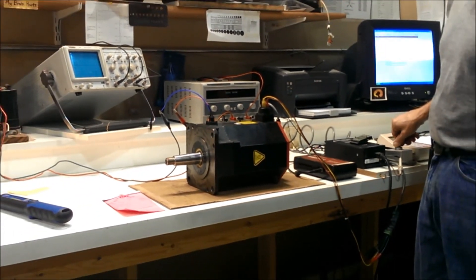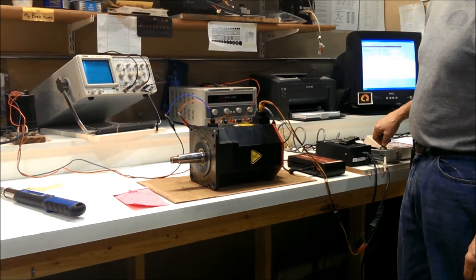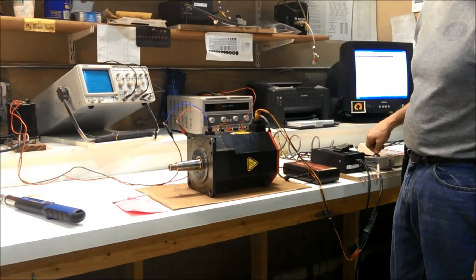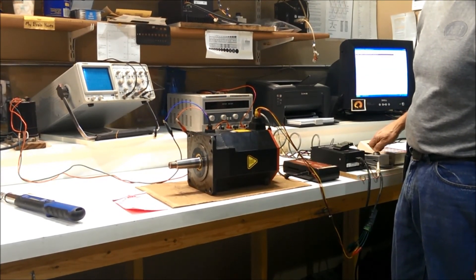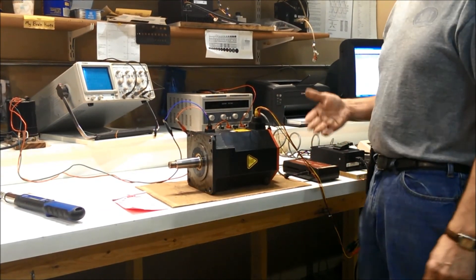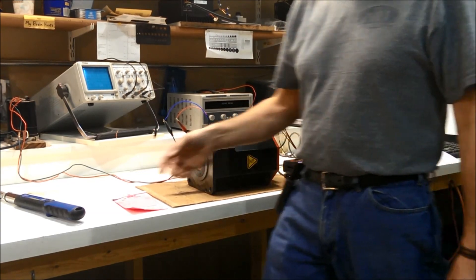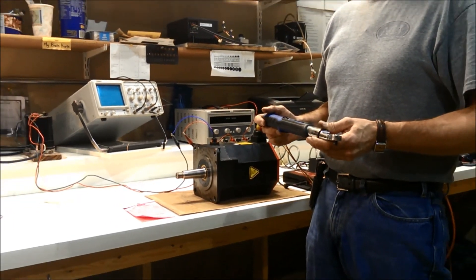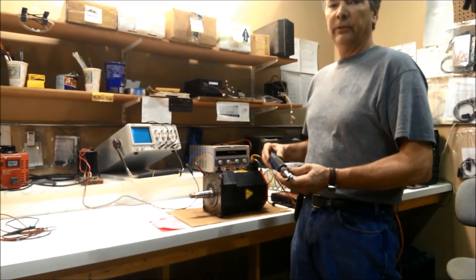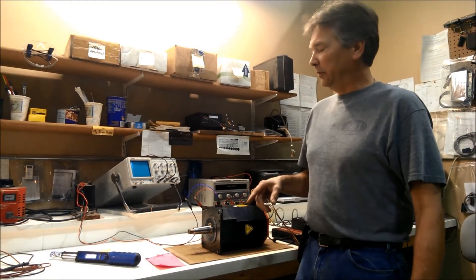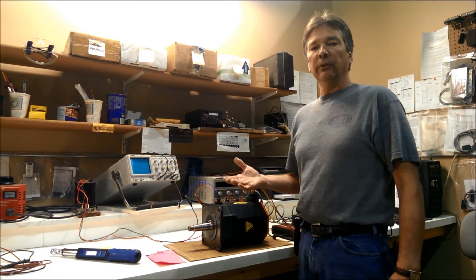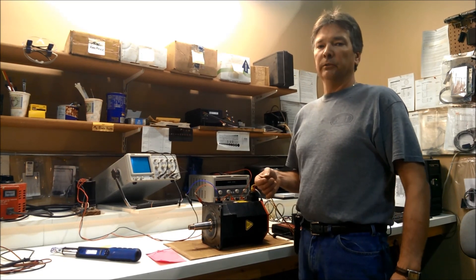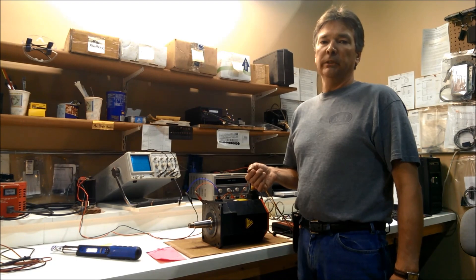And we'll rotate it at factory specs and then we'll also do a torque test on it to make sure that the motor magnets are up to the proper strength. The way we do that is we'll rotate the motor in much the same fashion. We'll actually attach a torque wrench to it, such as one that we have here, and compare the reading that we get from the torque wrench with the nameplate data or data that we have on hand. And then that way we know that the motor is up to the proper torque and that it will operate properly in the factory.